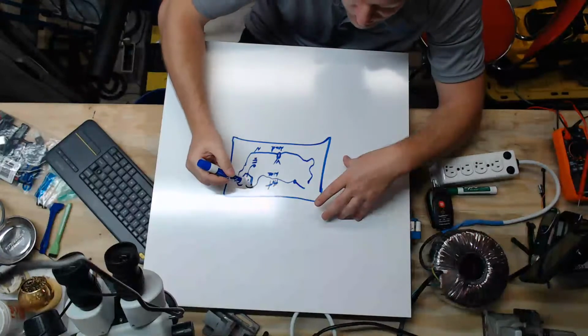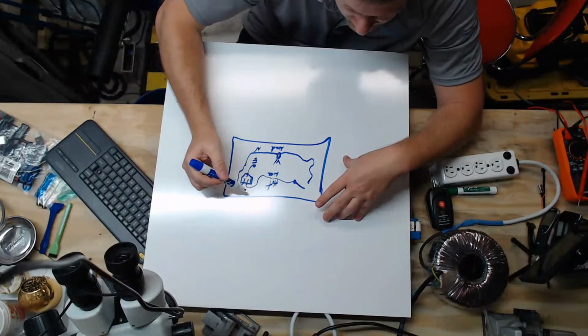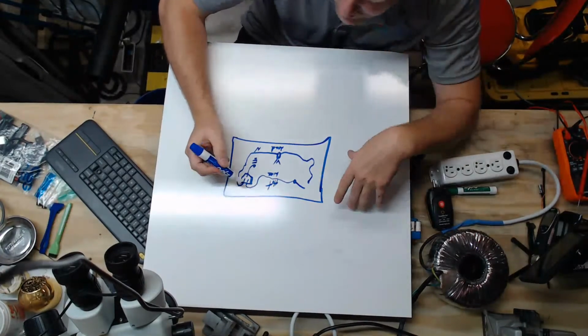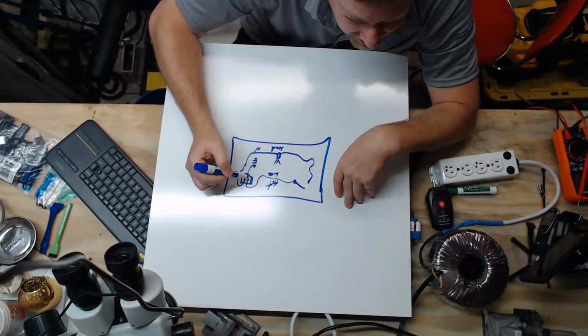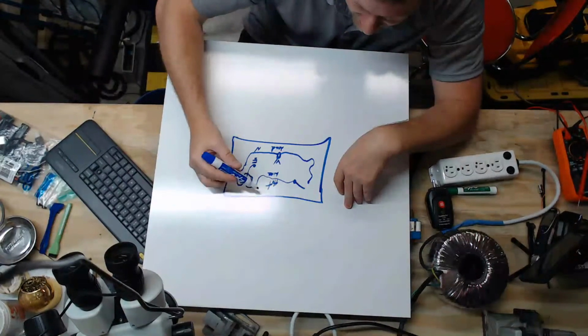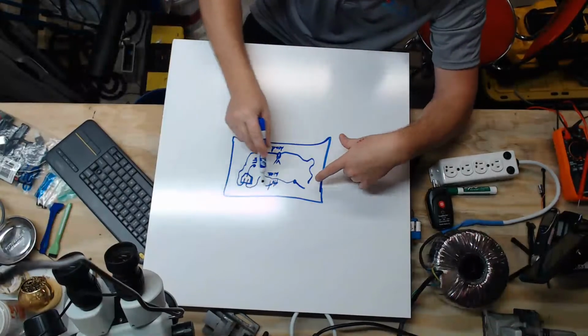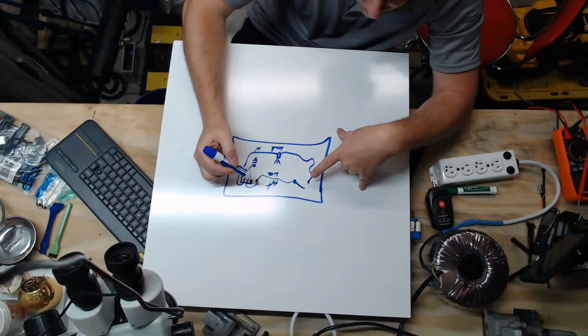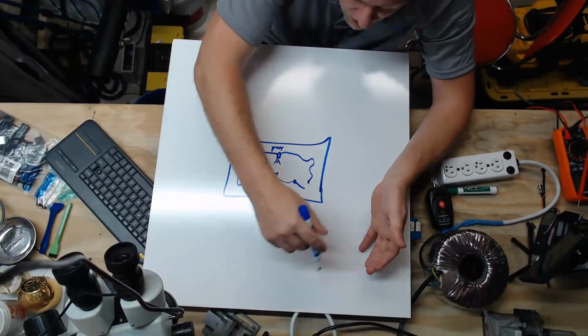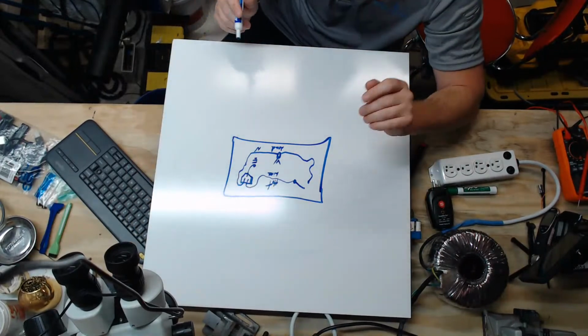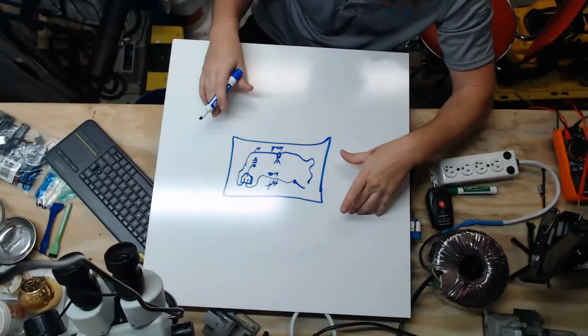And normally your power switch is going to be really close to your IEC power input to your medical device. Even though I drew it way over here, it's usually going to be really close, because you don't want hot wires running throughout your whole device. And this is why polarity matters.